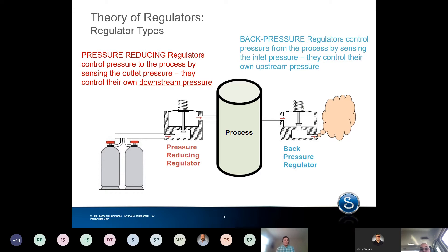On the other side, you have back pressure regulators. Where pressure reducing regulators drop pressure and control the outlet — what's downstream — kind of looking forward, back pressure regulators, as the name implies, look behind them. Back pressure regulators control the upstream pressure and keep that pressure within a specified limit. You can use them to relieve excess pressure.